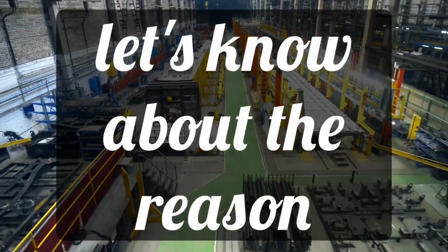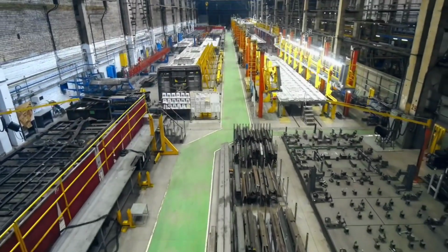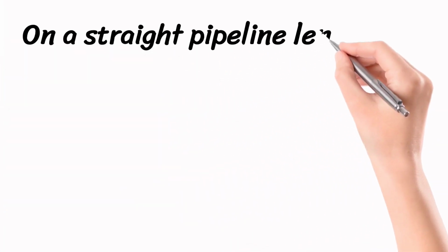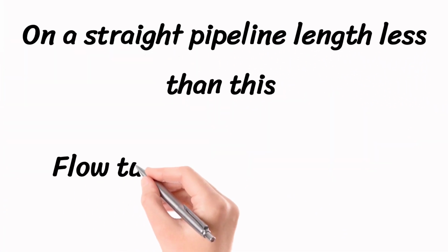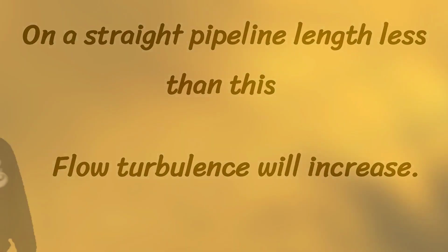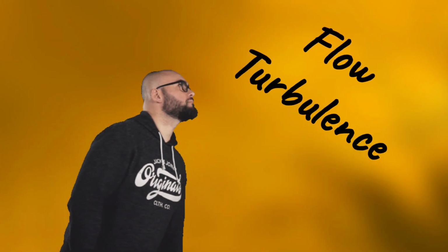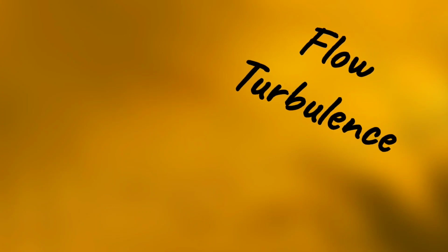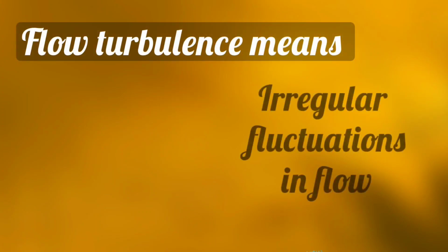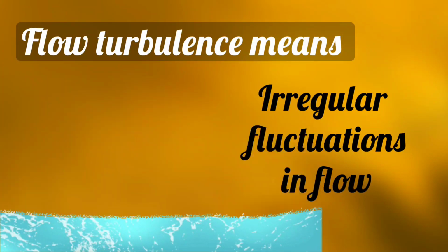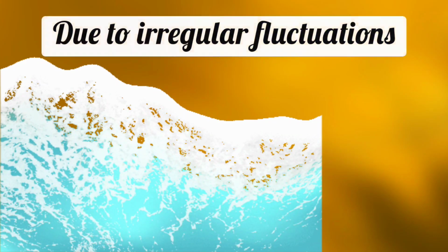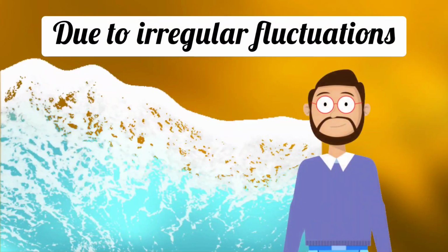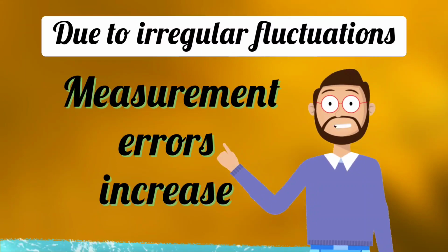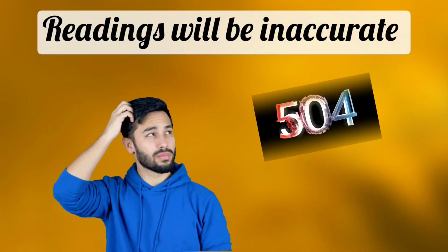Let me explain the reason behind this. On a straight pipeline length less than this, flow turbulence will increase. Now you will ask, what is this flow turbulence? Flow turbulence means irregular fluctuations in flow. And due to irregular fluctuations, measurement errors increase, meaning readings will not show correctly.